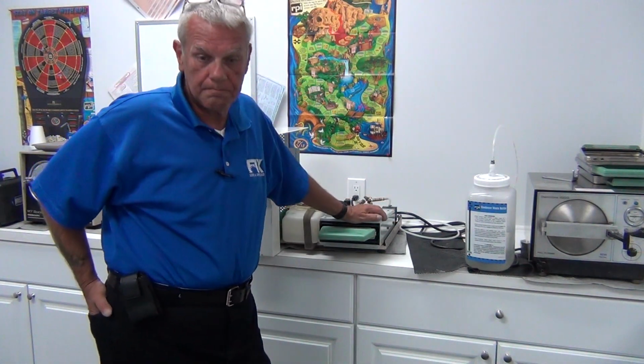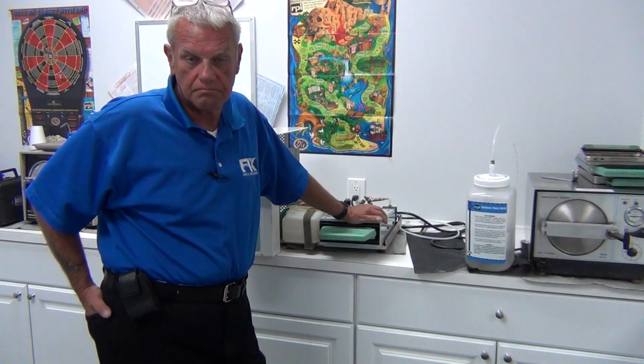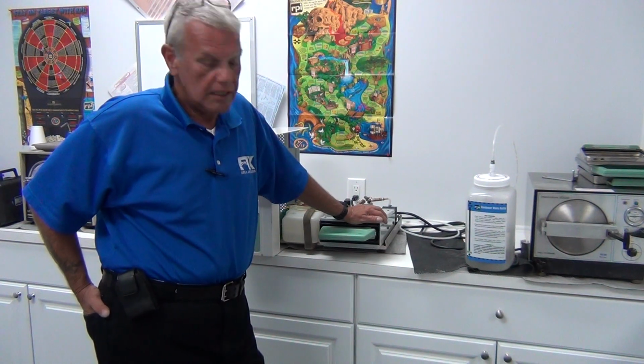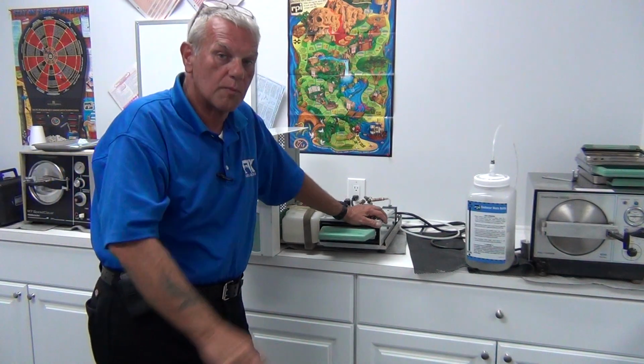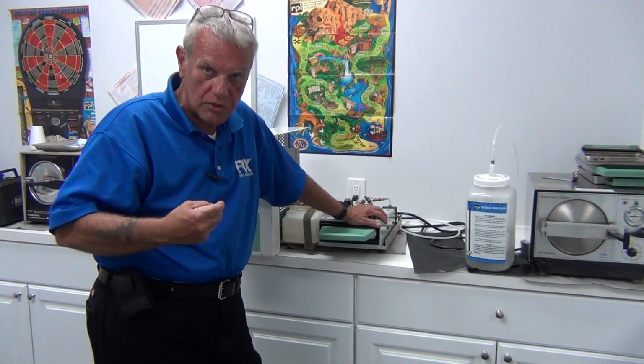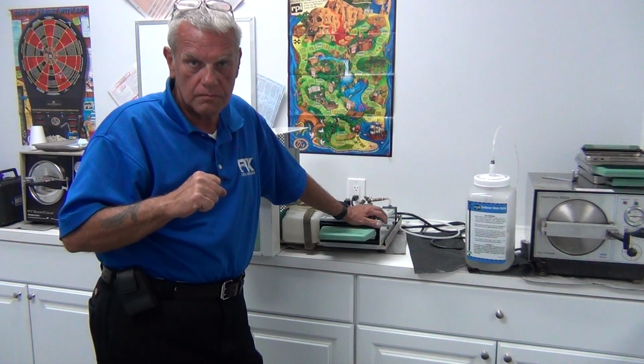RPI makes a product called Jet Dry or Stat Dry that you spray in the cassette to keep the cassette shiny. That's about the only ancillary product you can buy to maintain this machine. The Statim sterilizer only uses 1 dose of water per cycle. Unlike your big automatics that use the water, vent the water out into the reservoir and you reuse the water, this only uses 1 dose of water per cycle. So consequently, you do not get dirty cassettes, you do not get dirty boilers.